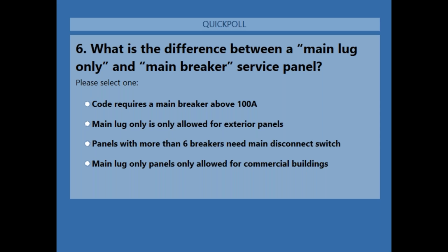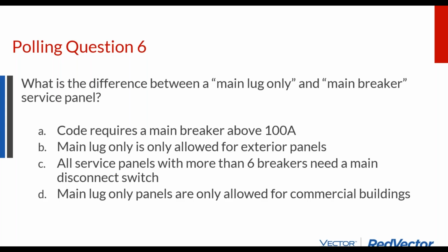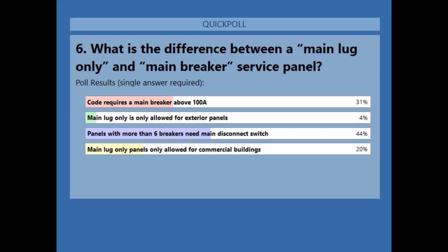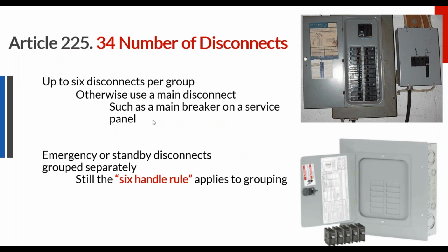So we have a couple of different questions here. I'm going to close it. Now I'm going to share it. And so what we have is the answer is panels with more than 6 breakers need a main disconnect switch. So that is the rule. It's called the 6-handle rule. And it says once you count up all these breakers that you're trying to turn off to power down the whole building or whatever is powering this panel, once you get more than 6 switches, then you need to have a main breaker. And so these main lug only panels are generally smaller with fewer breaker slots because there's only so much you can fit on them before you would need a main breaker switch.